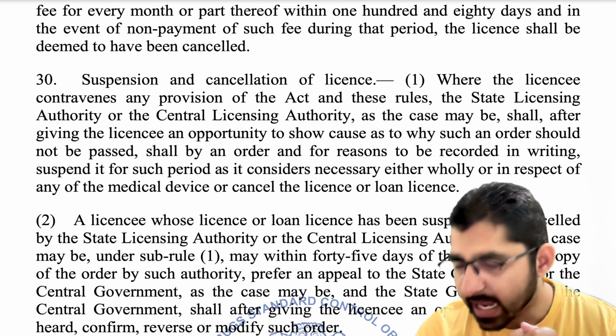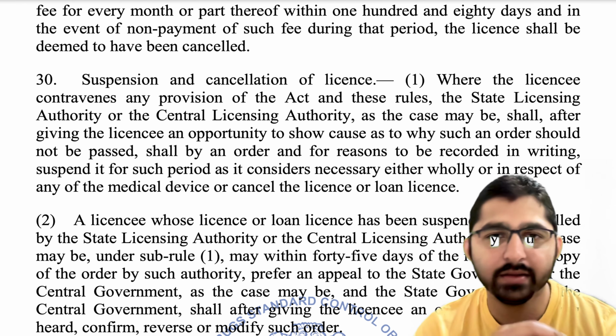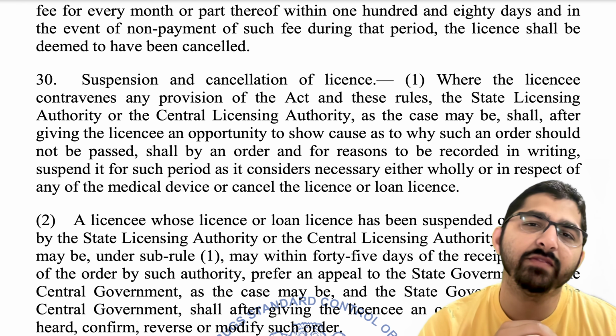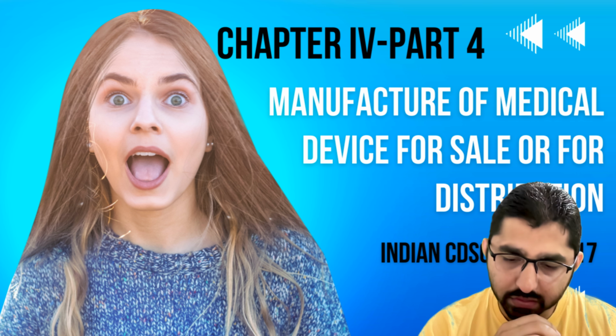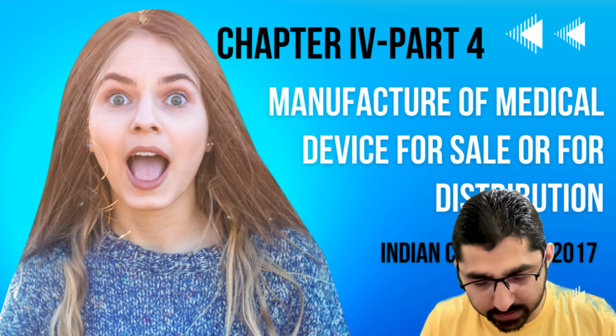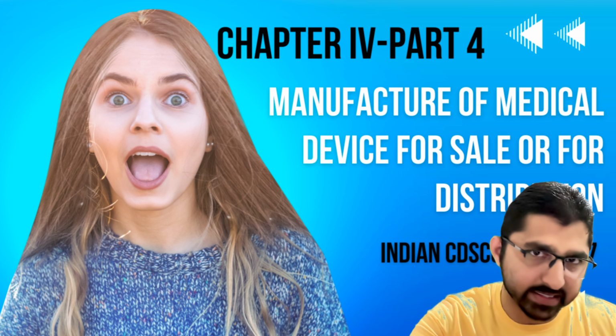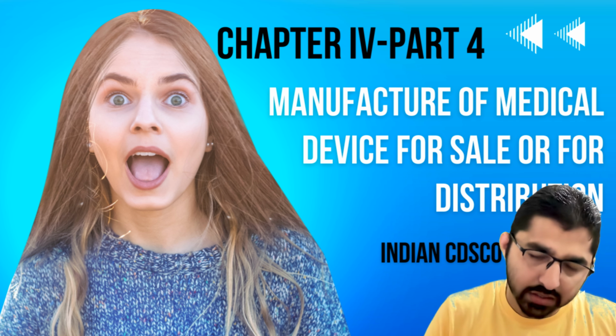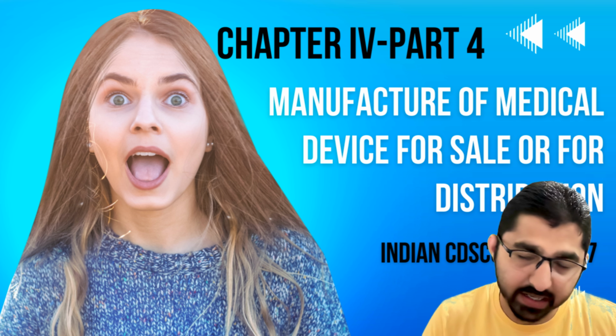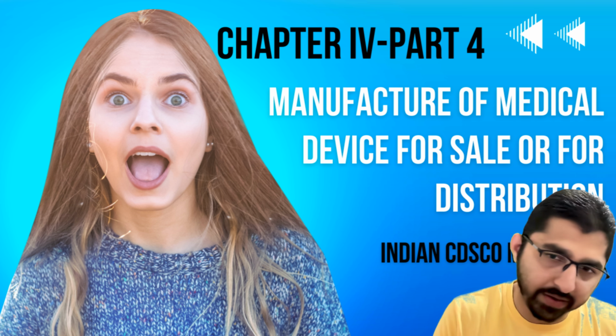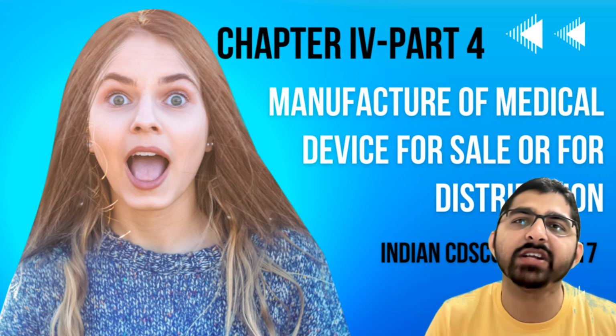So let's say I got the license from the Indian CDSCO. Now the time came where I need to pay the required fee. Let's say my license is expiring today. From today I'll have a grace period of 180 days, which means a grace period of 6 months. So in the next 6 months I'll have a chance to pay the fee, but with a penalty fee at a rate of 2% every month. But after 180 days, if I'm not able to pay the fee, my license shall be cancelled by the CDSCO. So this is very simple.